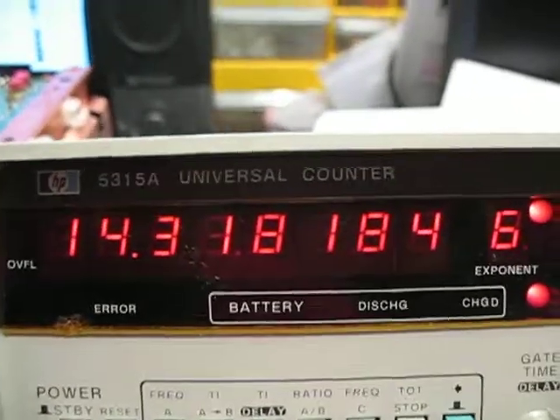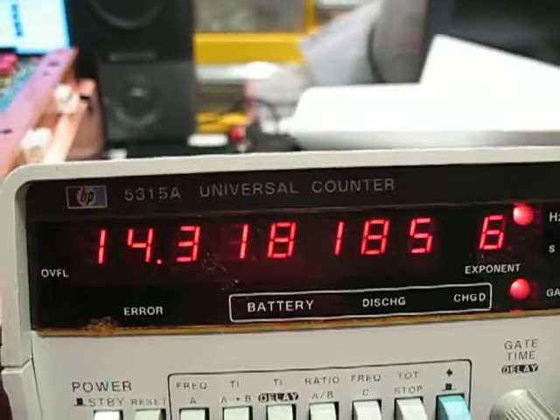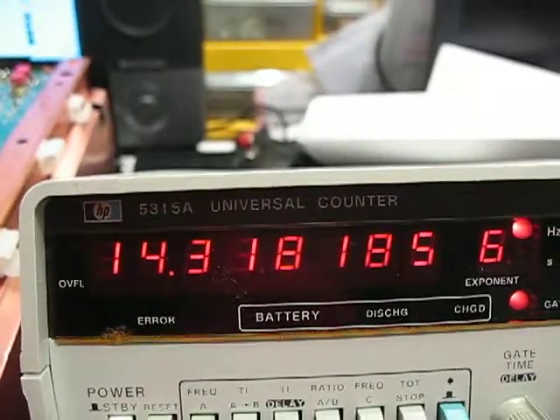This HP 5315A actually has the TCXO option, so it's got a temperature-stabilized oscillator as well. And it's been calibrated, so it's right on the money.